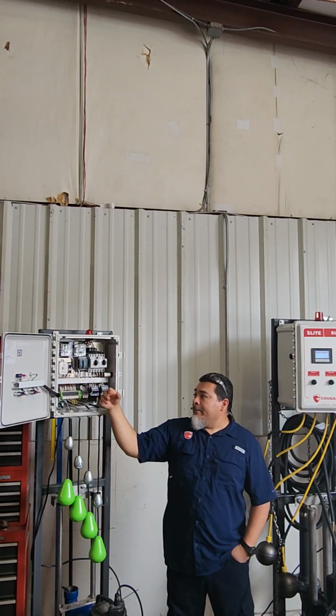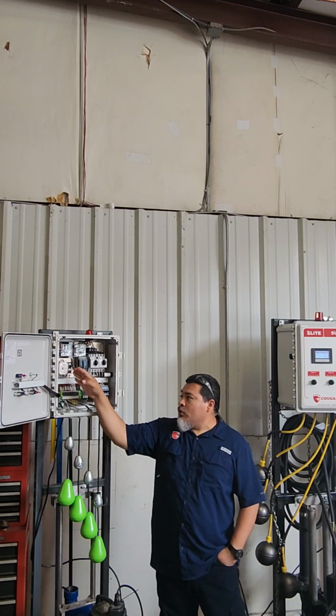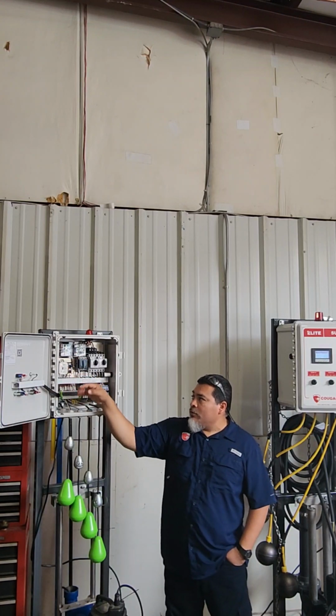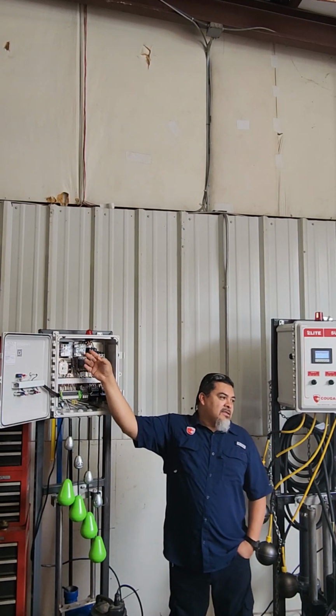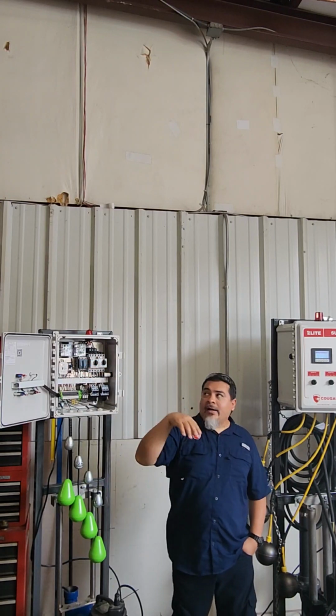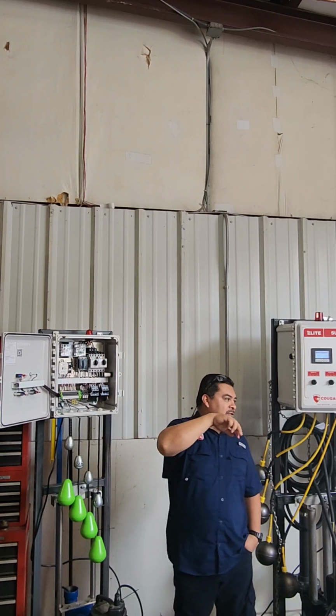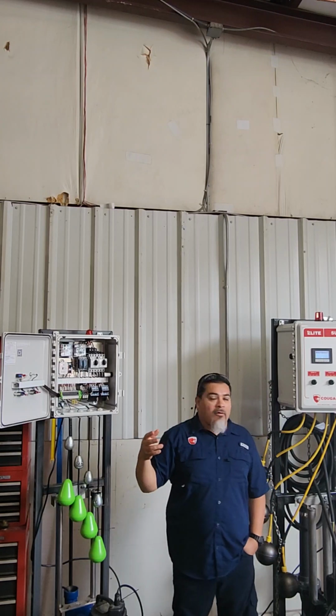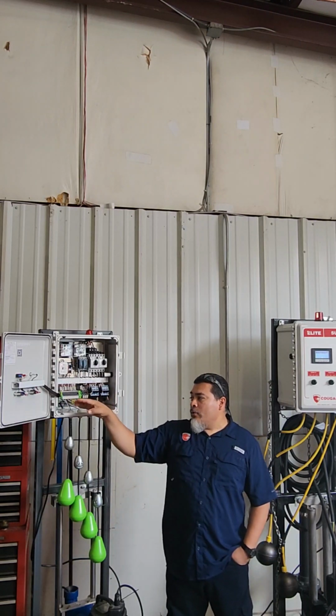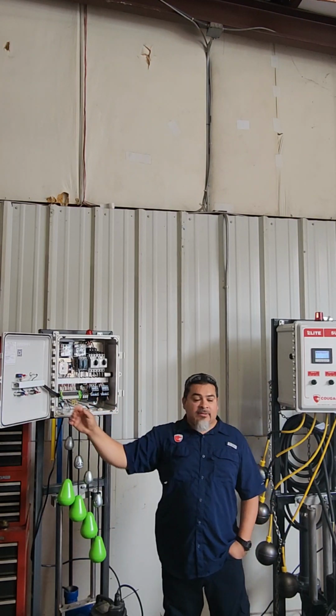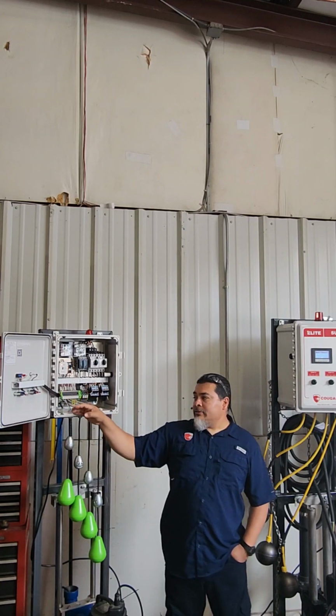All right. After that, of course, you want to check your 120. Make sure you do have your 120. Look and see if there are fuses. If there are, make sure your main power's off. Just check continuity between each fuse to make sure they all work. After that, check to see if your pump does come on. Then you start going through your floats.